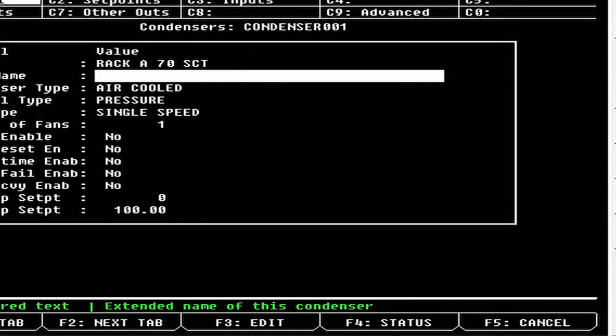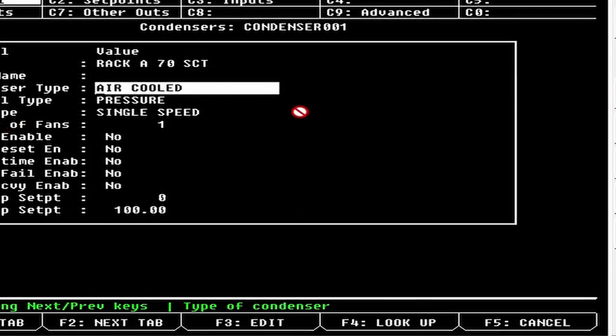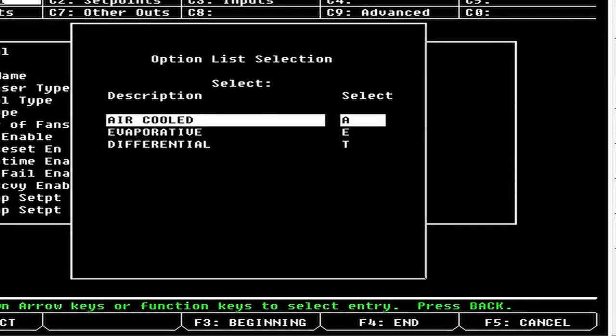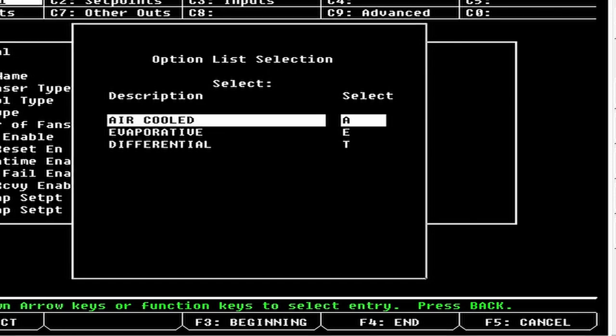Come down here to Condenser Type. If you hit F4 Lookup, you'll have three options: Air Cooled, which is the standard condenser where the set point stays the same — this is an older school setup for just maintaining pressure. Evaporative would be a cooling tower. And Differential, which we're going to go over today. Each one makes different options appear — evaporative gives you pump options, air cooled gives standard options, differential is for floating head pressure.